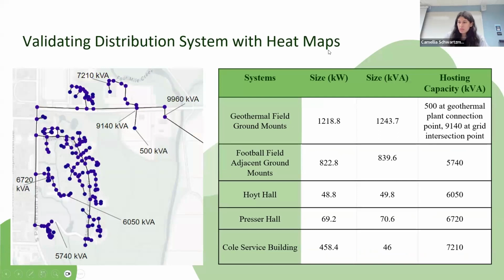So to validate our systems, to make sure they weren't overloading the grid, we used the system heat maps to check each node individually. The only issue that arose that you can see in this hosting capacity summary was the one at the grid node at the geothermal plant. We're saying that they need to upgrade this line to about 2,500 kVA to avoid the risk of any overvoltage events. And if this is upgraded, this would satisfy about 50% of hosting capacity for the geothermal solar system. And with this upgrade, we've lowered the risk of overvoltage events, and there's a lower possibility of other grid issues as well.